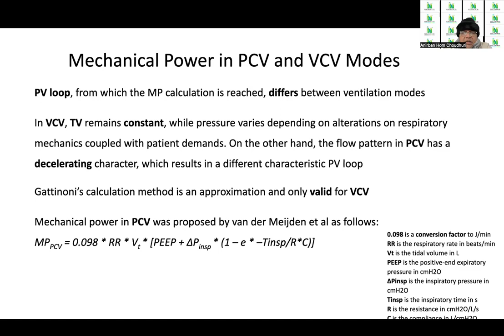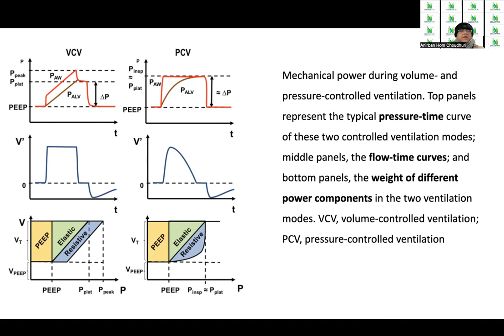Now, if we look into these two modes, and if the top panel represents the pressure-time curve, the middle panel the flow-time curve, and the bottom panel the weight of the different power components, we can clearly see that in volume control versus pressure control, the resistive component is clearly different. The elastic component may or may not be different based upon the amount of ventilatory support in pressure control, and the PEEP, of course, remains independent. Therefore, these two equations need to be calculated separately if the patient happens to be in different modes of ventilation at different points of time.